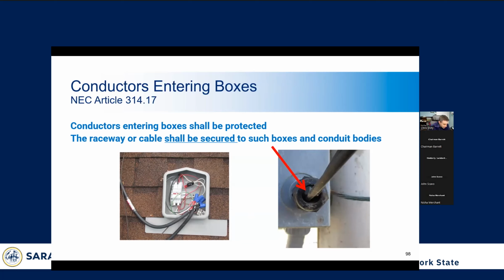Here we have a situation where this is pretty common. The fitting used to provide strain relief for the wire coming into this junction box was not. It looks like it's damaged actually, but it isn't snug with the wire, so it's not going to really provide any good. It's not going to stop water from getting in. It's not going to provide any kind of strain relief. So that should be disconnected and reinstalled.